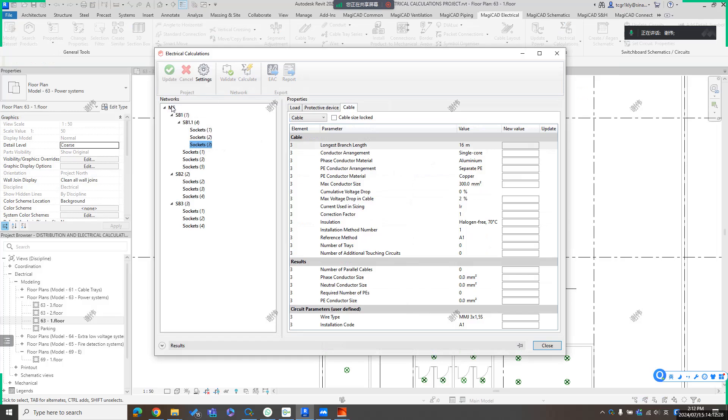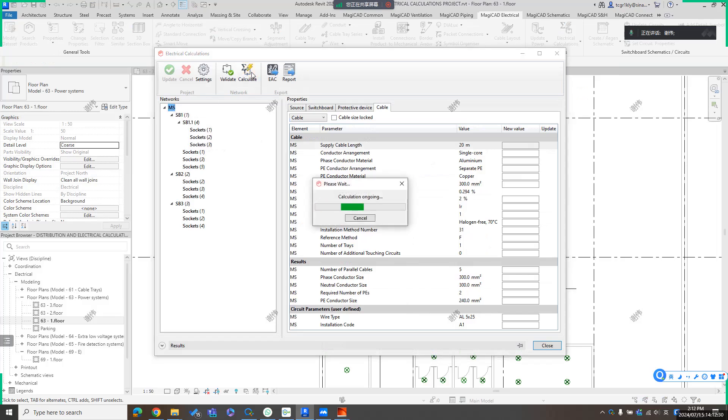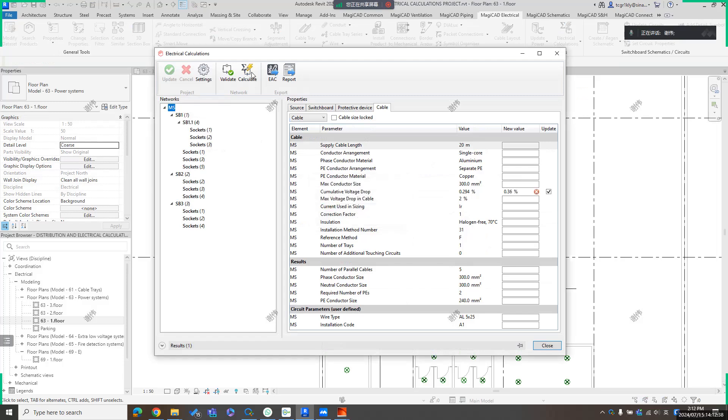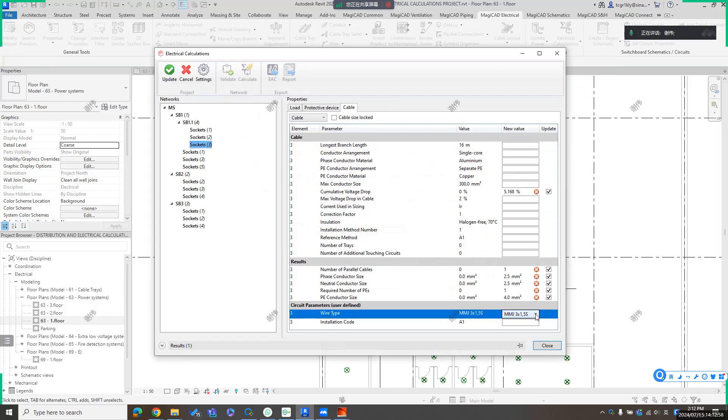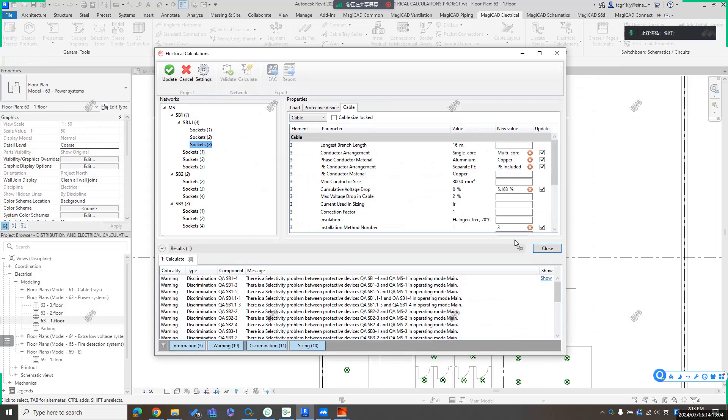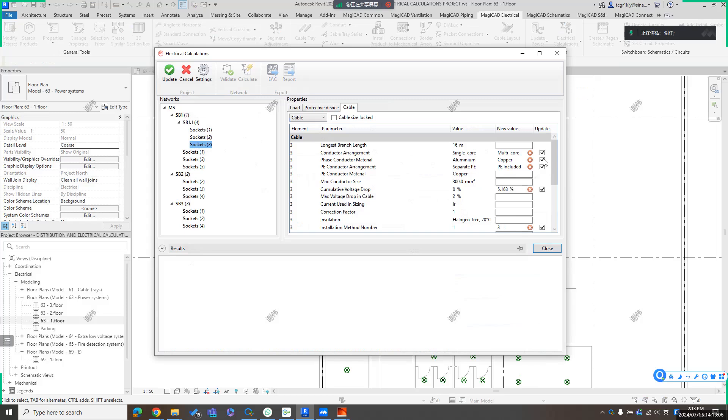So here we can use MagiCAD function to calculate the result and wait for seconds. We can get the result like this. So here for this circuit, the new circuit, you have got the cumulative voltage drop, like 5%, and you can also get some result of cables. And here you can also define the wire type as you need. For example, I want to define to this one. Okay, got it.